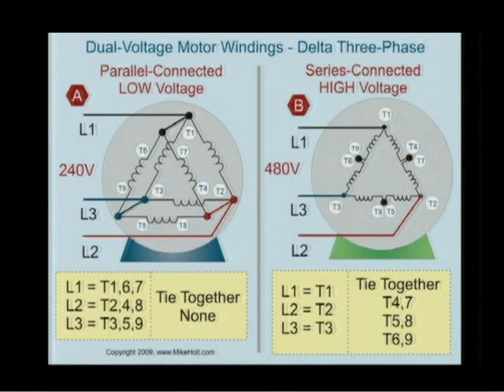I didn't have the education when I was first working, but I remember one time a motor where the leads were cut. There was nothing put on the leads. So what do you do if you get to a motor and it doesn't have any of the numbers? Do you just tell them, you better get another motor, or you better get somebody to identify? What do you do? Because how would you know if it was a Y connection or a delta connection? An ohmmeter can help you get that far to figure out if it's a Y or a delta. Because with the delta, you're going to have 3 sets of 3 leads.